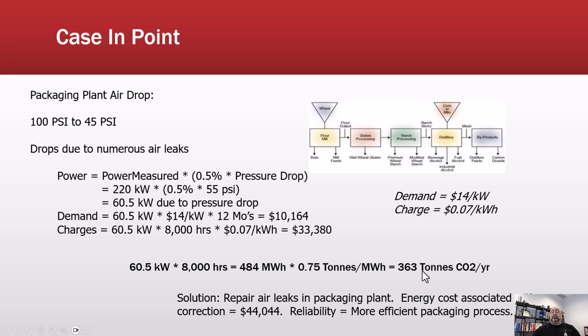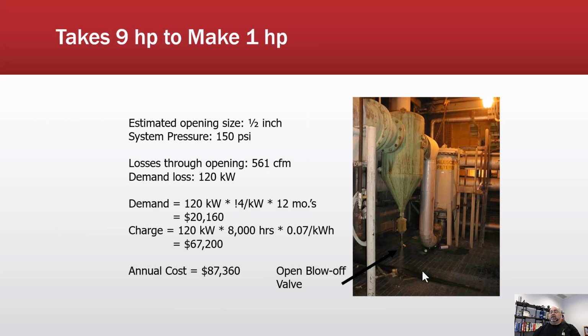In fact, part of what we discovered in the 1990s in all of the challenge programs associated with the Department of Energy was that maintenance and reliability were the number one methods for reducing energy in a plant, even over the application of energy efficient technologies. So let's take a look at this particular one. Compressed air systems, it takes 9 horsepower to make 1 horsepower. In another area of the same plant, we had a 1/2 inch opening, 150 psi. There's a calculation for coming up with the amount of air lost through that opening. In this case, it was 120 kilowatts coming through there.